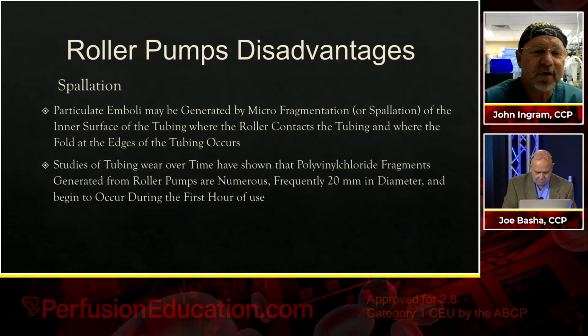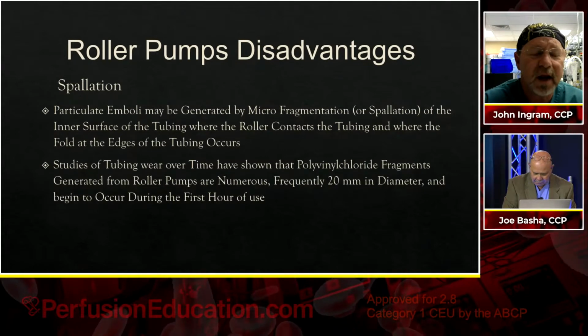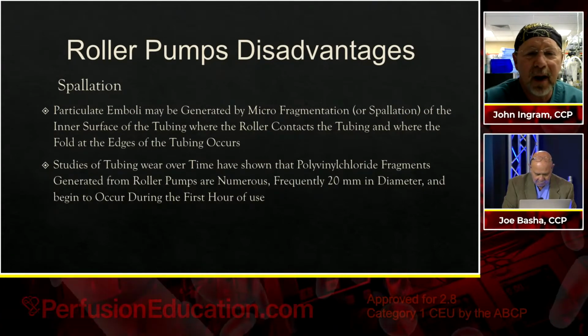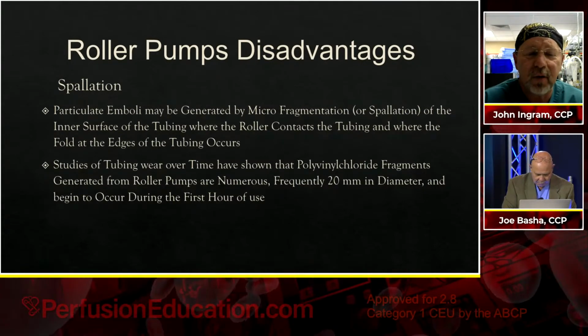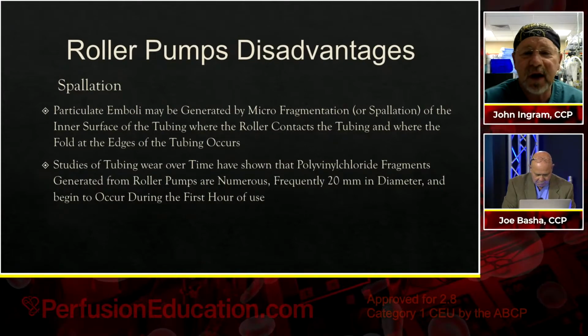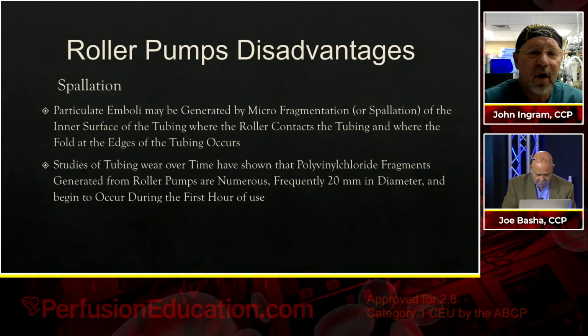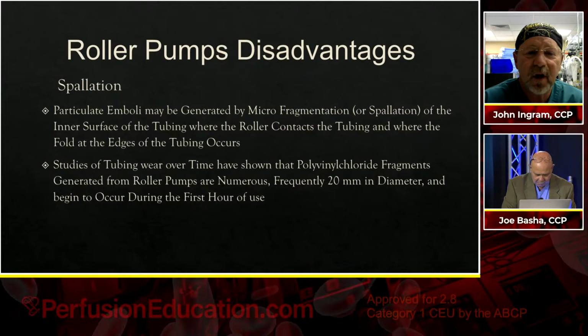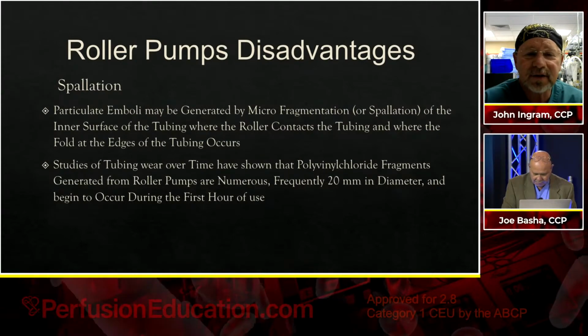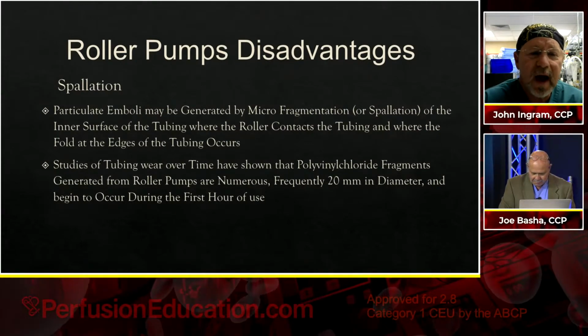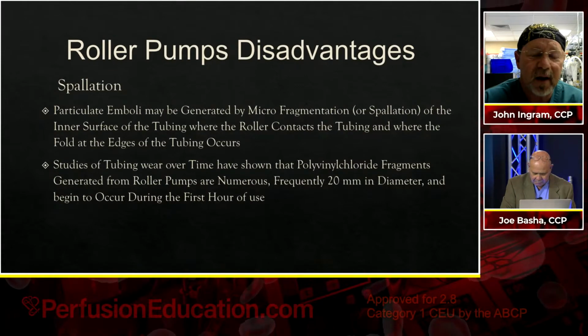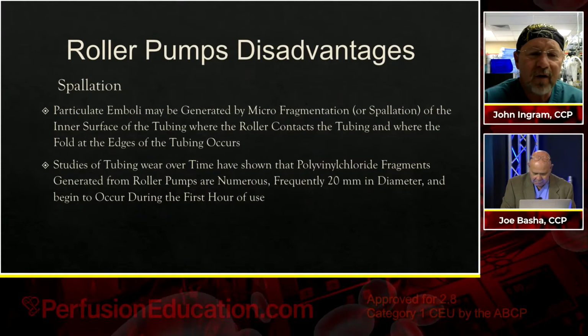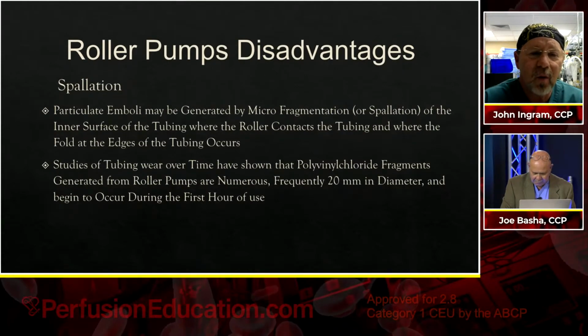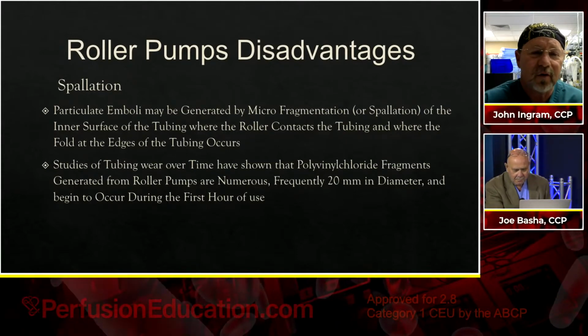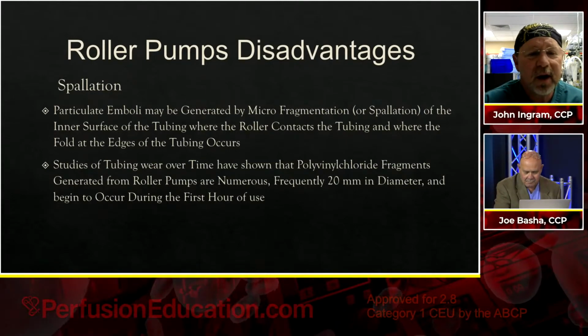Yeah, spallation. There's another disadvantage of the roller pump: particulate emboli may be generated by micro fragmentation, called spallation, of the inner surface of the tubing where the roller contacts the tubing, and where the fold occurs at the edges, the top and bottom of the tubing, where it folds together. You can have the spallation, okay?